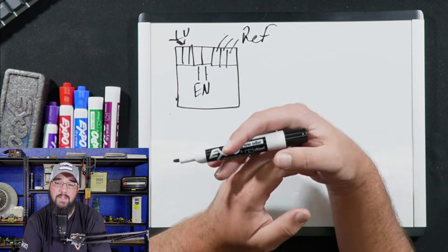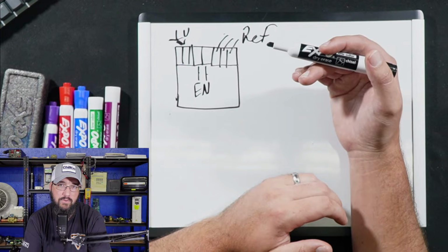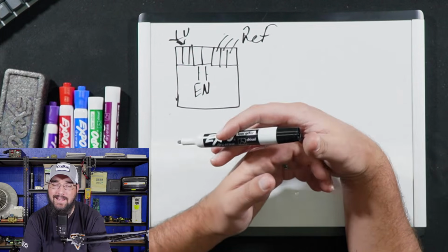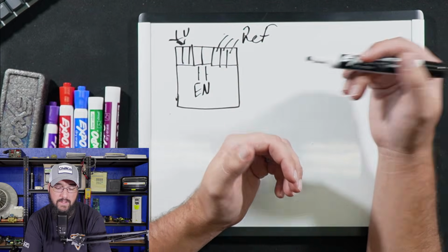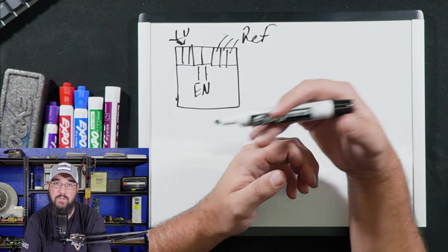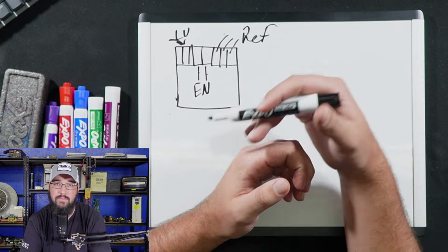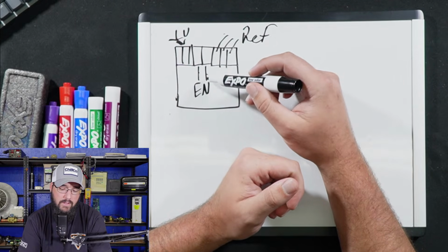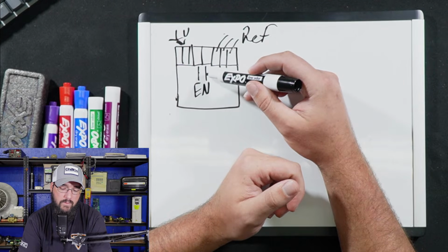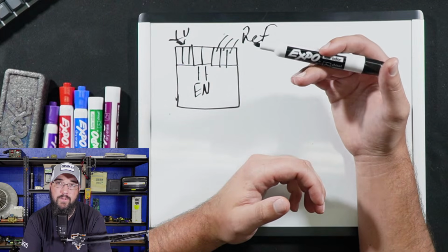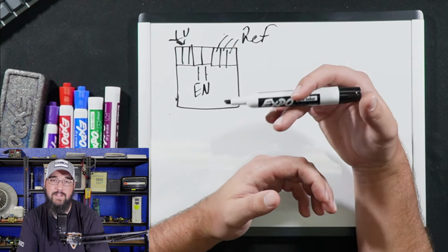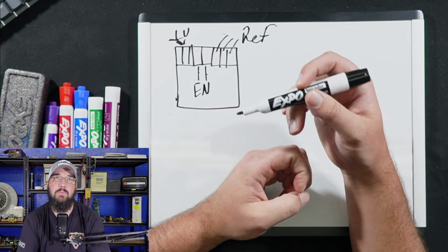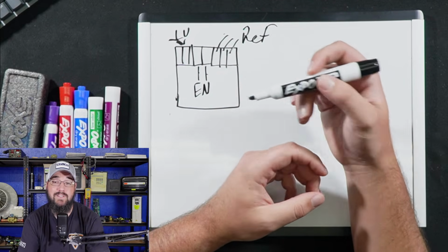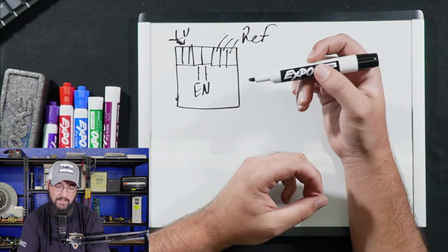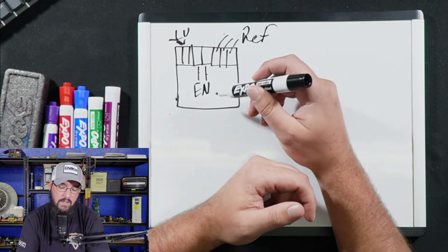When he had a fan failure or was able to simulate it, it didn't cause the entire fan deck to go down like it was when this enable signal was having a failure or a fault. That's partially why it was so intermittent as well, because he wasn't able to replicate it, but it was still happening pretty consistently from the way he described it.